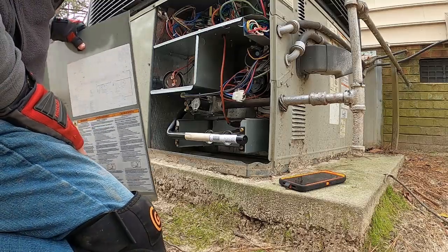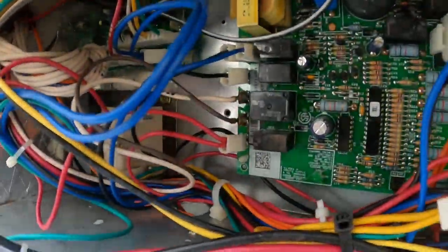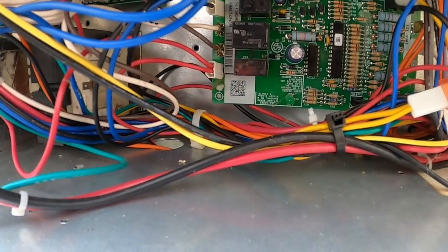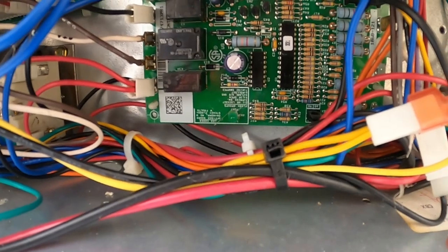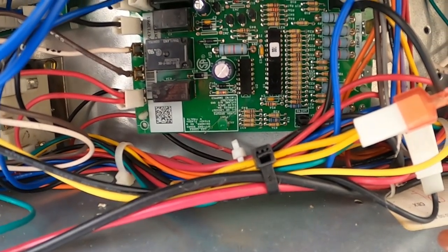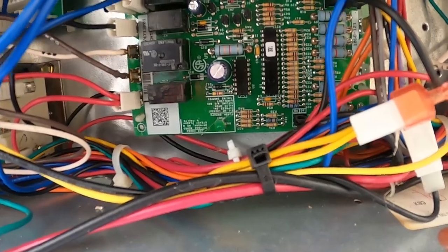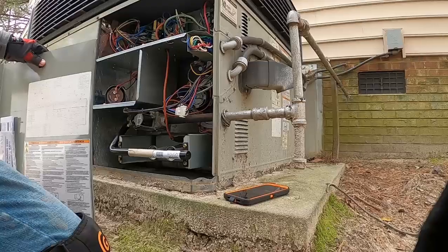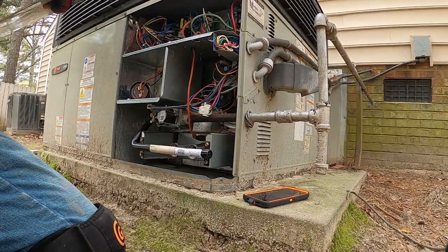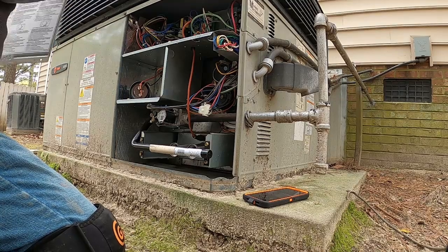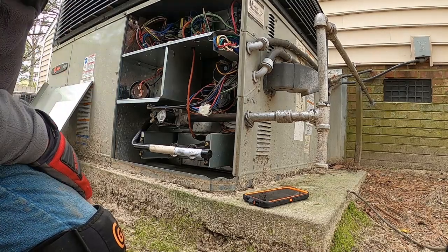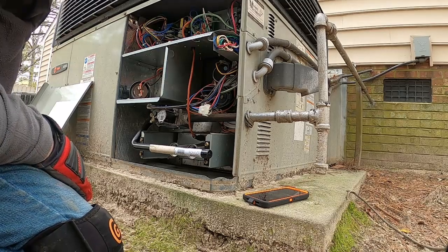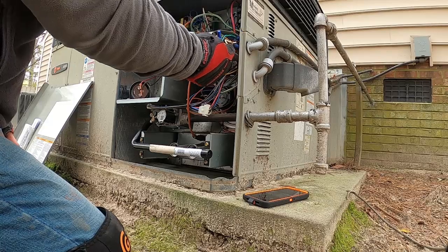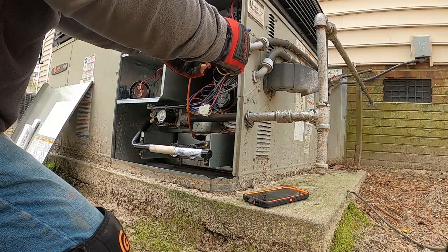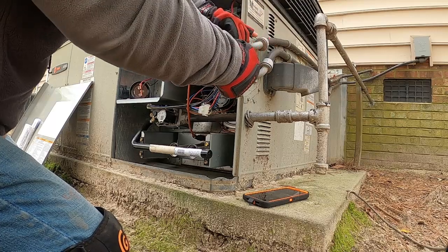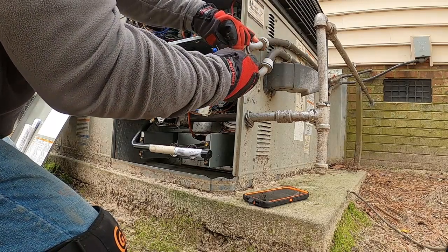So let's see what we got for our fault code here. 1, 2, 3. So let's check our fault code. We have a pressure switch fault on this thing. So we are getting a call. Let me confirm that real quick. This is a 2-stage system.